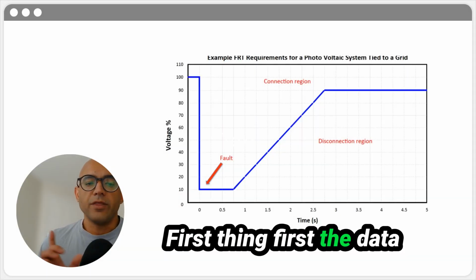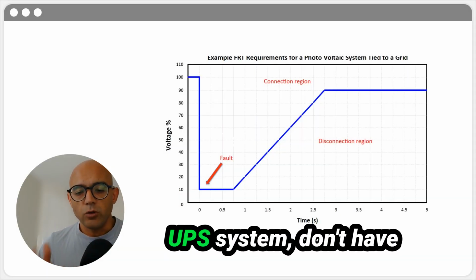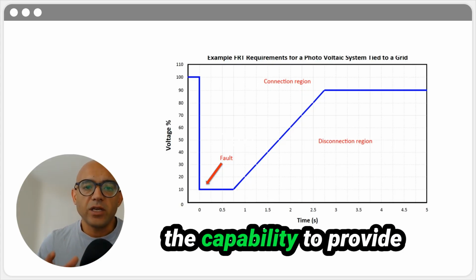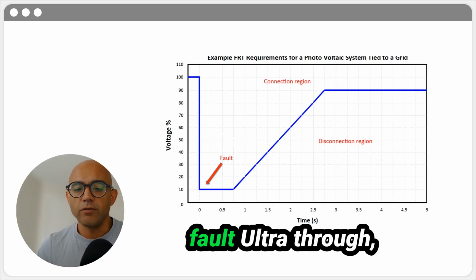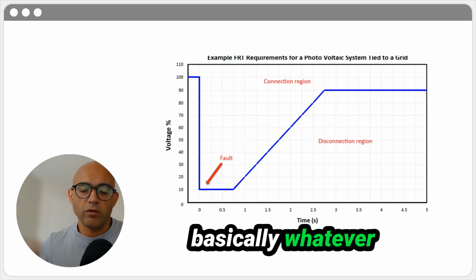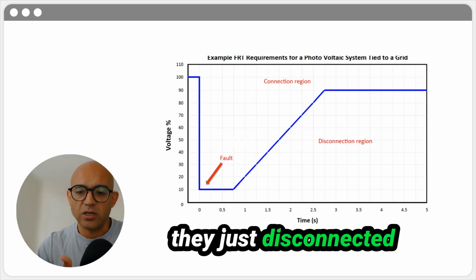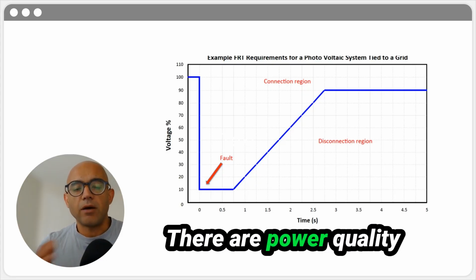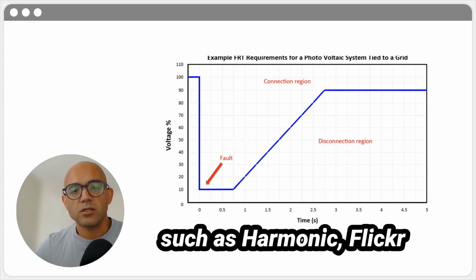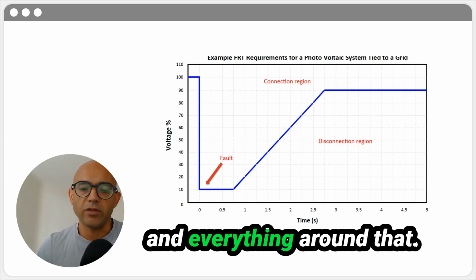First thing first, the data centers by themselves, or the UPS system, don't have the capability to provide fault ride-through. Basically, whatever happens to the system, they just disconnect from the network. There are also power quality issues with these devices, such as harmonics, flicker, and everything around that.